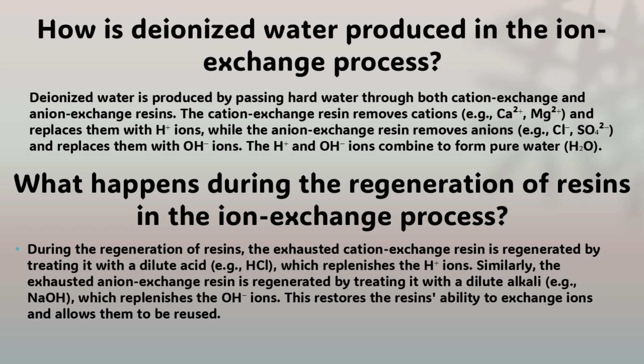The next question is question number 48. What happens during the regeneration of resins in the ion exchange process? The answer to this question is: during the regeneration of resins, the exhausted cation exchange resin is regenerated by treating it with a dilute acid, example HCl, which replenishes the H+ ions. Similarly, the exhausted anion exchange resin is regenerated by treating it with a dilute alkali, example NaOH, which replenishes the OH- ions. This restores the resin's ability to exchange ions and allows them to be reused.